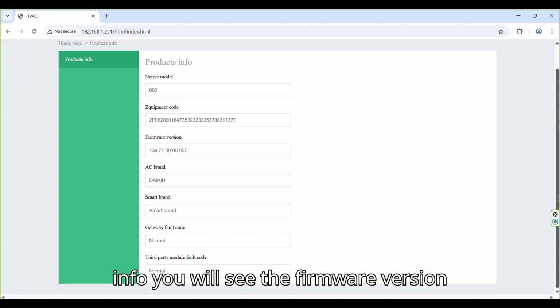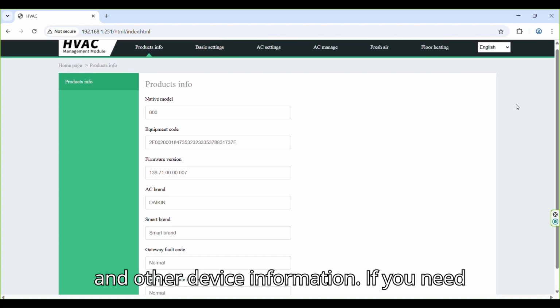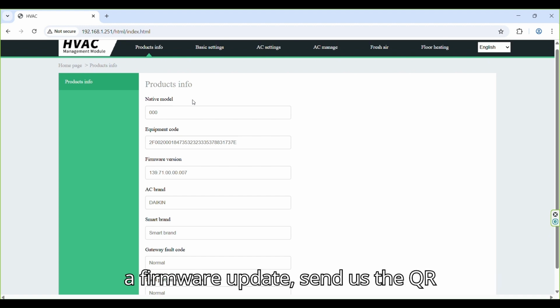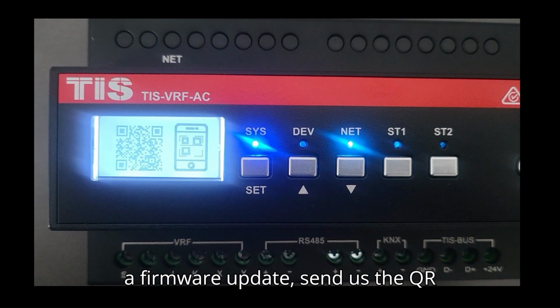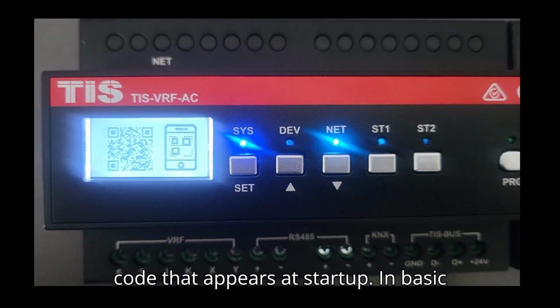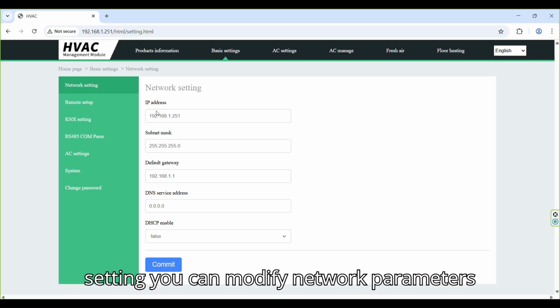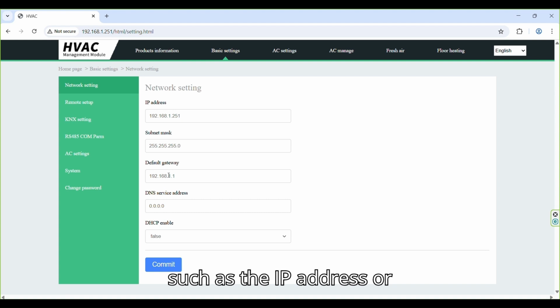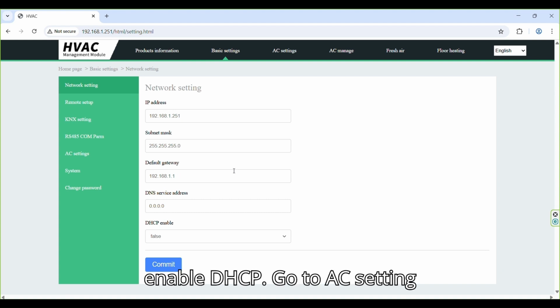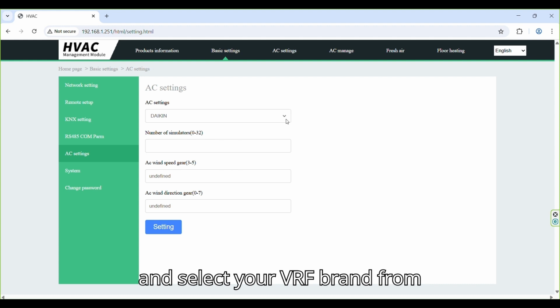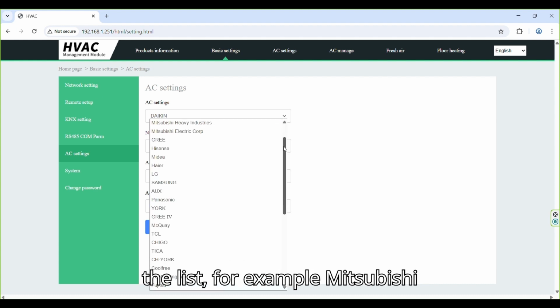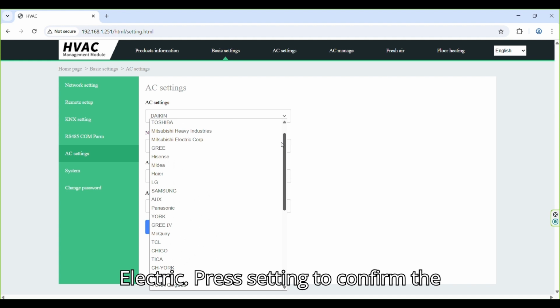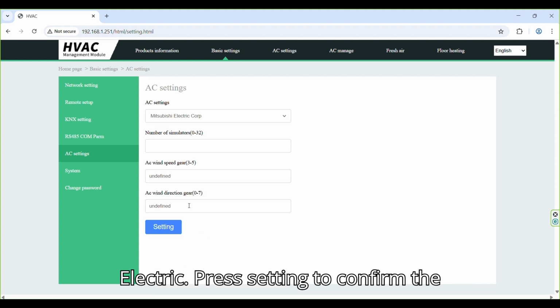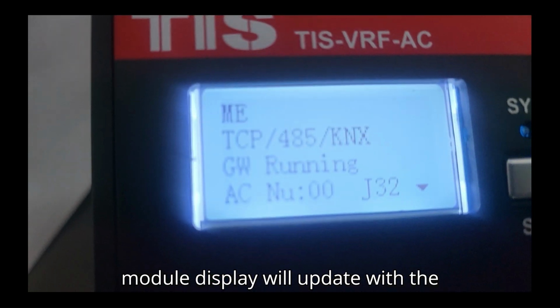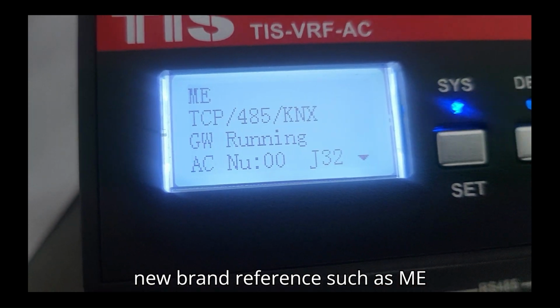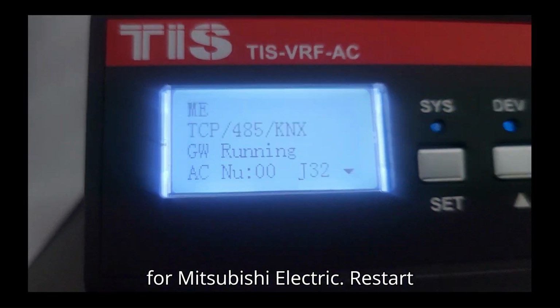Under Product Info, you will see the firmware version and other device information. If you need a firmware update, send us the QR code that appears at startup. In Basic Setting, you can modify network parameters such as the IP address or enable DHCP. Go to AC Setting and select your VRF brand from the list, for example, Mitsubishi Electric. Press Setting to confirm. The module display will update with the new brand reference, such as ME for Mitsubishi Electric.